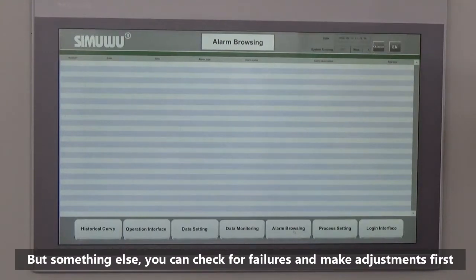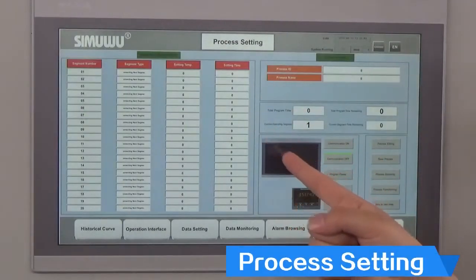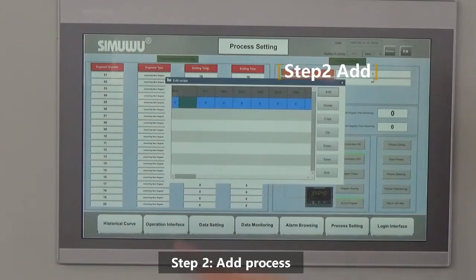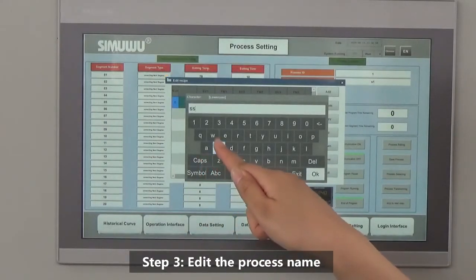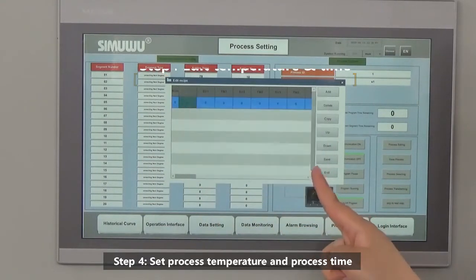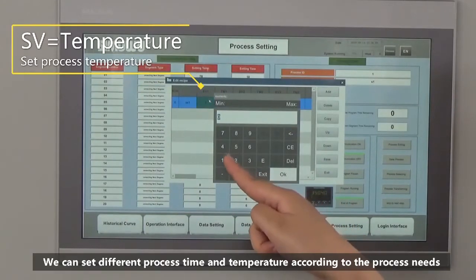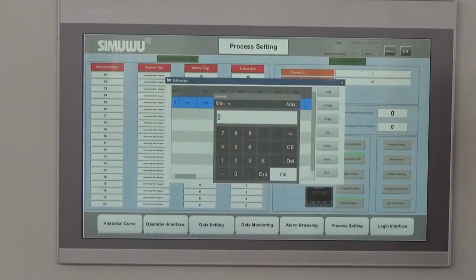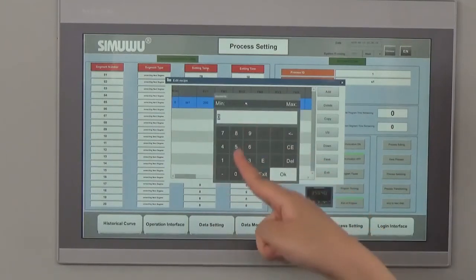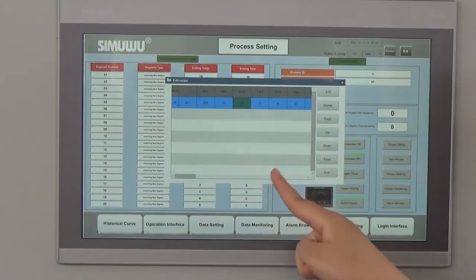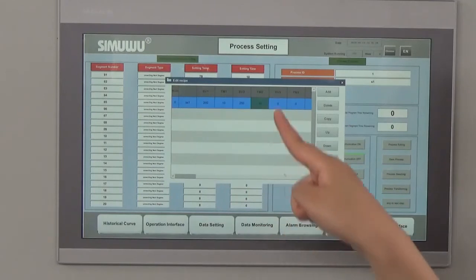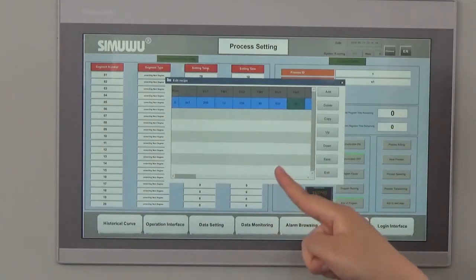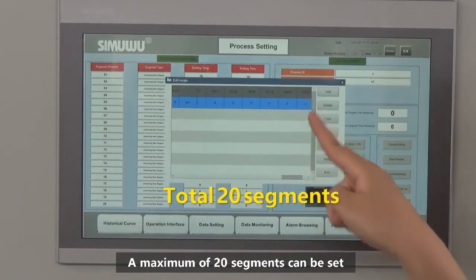If it is not over-temperature or over-pressure but something else, you can check the failures and make adjustments first. The sixth module is process setting. Step 1: edit process. Step 2: add process. Step 3: edit process name. Step 4: set process temperature and process time. We can set different process times and temperatures according to the process needs. A maximum of 20 segments can be set.